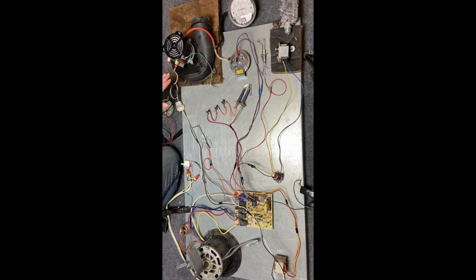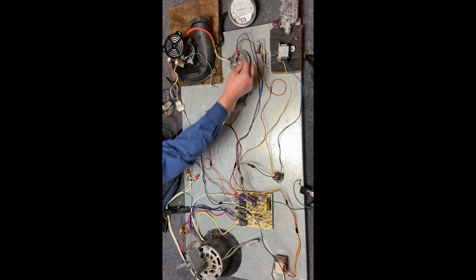Now, is that enough amps? We have to compare it to the tag of the motor. We want to make sure this amperage is under the amps here. We see our spark igniter engaging, no flame, so it kicked it back out.